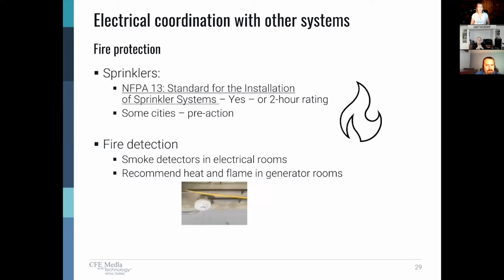So fire protection, this is also a question. People are like, oh, I don't want sprinklers in my main electrical room. Okay, there's a choice you have to make. The NFPA basically says that sprinklers in a standard electrical room have to be provided, or you have to put in a 2-hour rating of the main room. So this is a discussion. Usually we do both. I mean, it's good engineering practice.